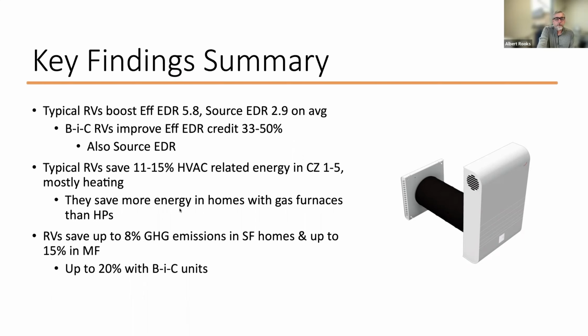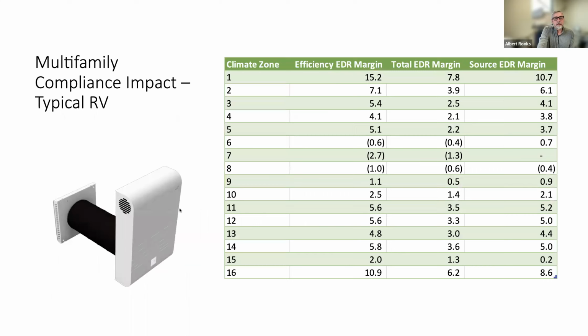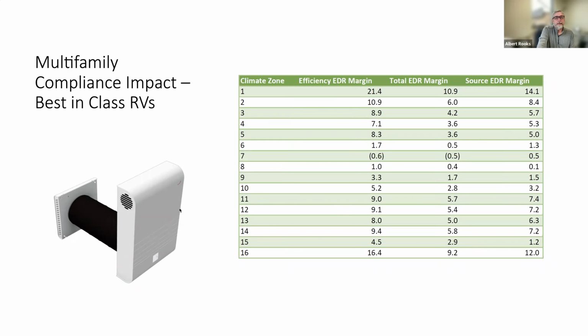But the impact on Title 24 is pretty substantial in a multifamily building in those extreme climate zones, right? Climate zones 1 and 2 give you an additional EDR margin of over 6%, 10%, right? This could be a pretty big impact. In climate zones 6, 7, and 8, we don't really need energy recovery. You don't have that many losses due to heat recovery, in both conserving heat in the building and preserving cooling in the building. In those climate zones, it's not meaningful, so we can pay more attention to airflow and how it affects humidity and occupant health. But in the extreme ends of the climate zones, it becomes a real factor.